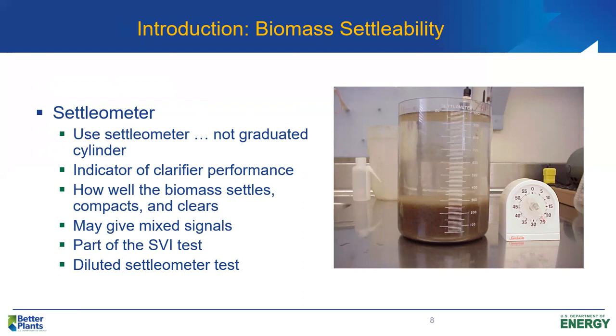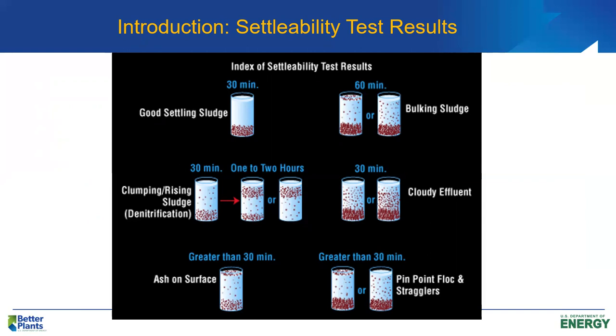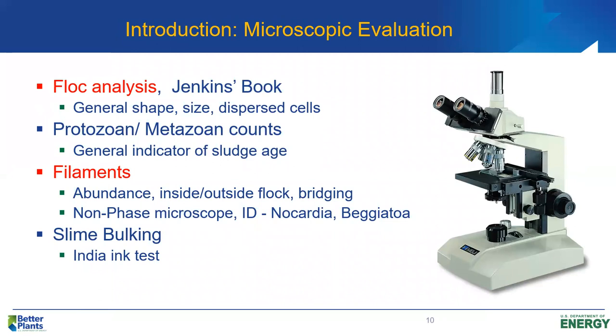If we do the diluted settleometer test and the sludge settles much better, that typically means we just have a glutted system — which is what that plant had. The sludge settled to about 250 mL/L with the diluted test, confirming they were running too high mixed liquor suspended solids and just needed to waste more sludge. On the other hand, if we do the diluted settleometer and the sludge doesn't settle better, that is usually an indication that we have filamentous bulking in our process.